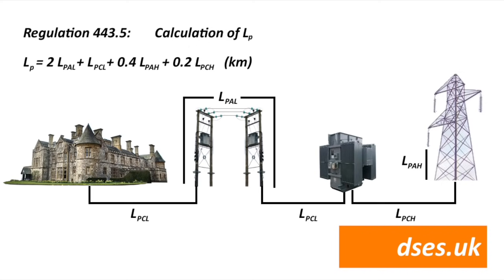It's not always going to look like this, but yeah, to perform this calculation I need to know these distances. Unless you're a developer building a new estate where these factors are known because you're involved in them physically being trenched in on your watch, then you're not going to be plugging any numbers into this formula with any kind of accuracy.